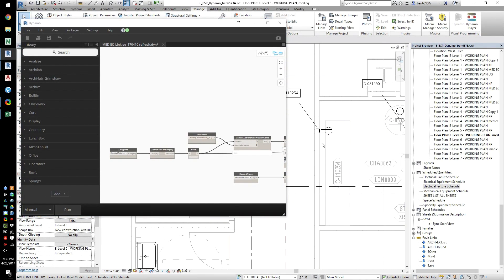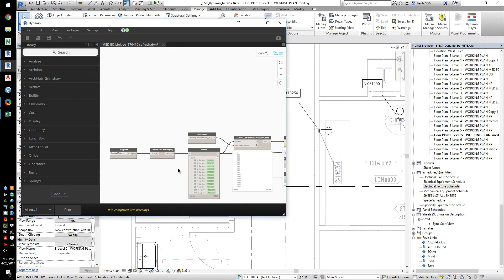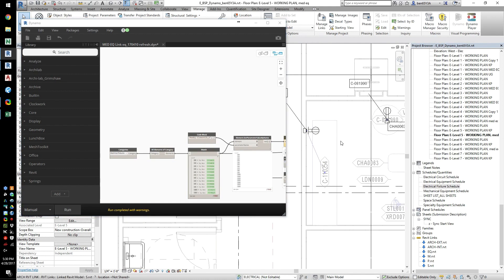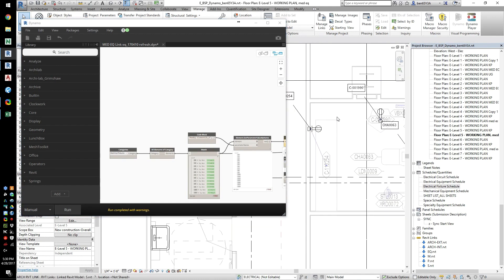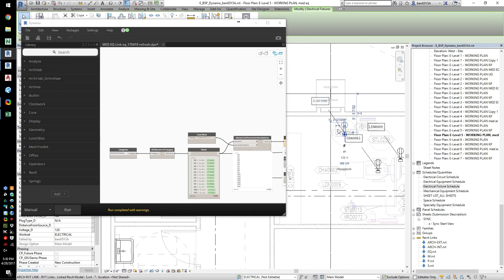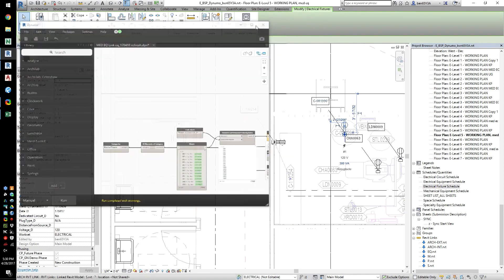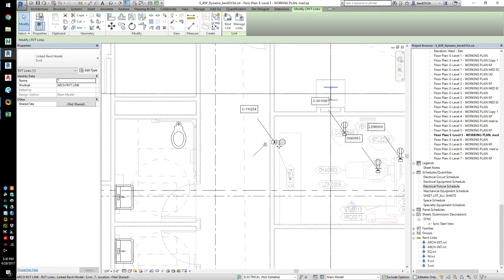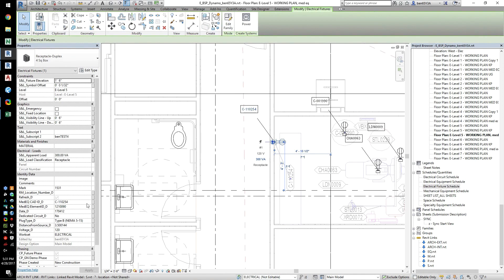Because our equipment and receptacle reference each other with a parameter, we can use Dynamo to check the distance between the two. If the distance is too large, we know there's been a change and we can fix it. This script even draws a line between the receptacle and equipment, so you can do a visual check.